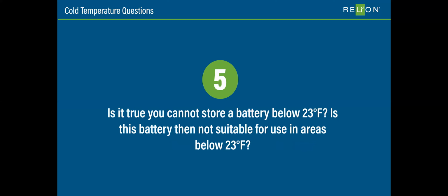Is it true you cannot store a battery below 23 degrees F? Does that mean the battery is not suitable for temperatures below 23 F? That's our recommended storage range, between 23 F and 95 F, which will preserve the battery and provide the longest life. Long-term storage outside that range is something you want to try to avoid if you can - it's unknown what really happens long-term or how much degradation there is in the battery. That's similar to all lead acid batteries too; you can't store them in freezing temperatures because they have liquid electrolyte that will freeze and damage the battery. So it's a good idea to continue that practice even with lithium batteries, but we've actually extended the temperature range down to 23 degrees Fahrenheit.